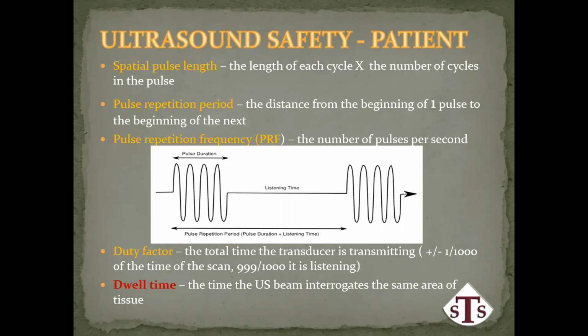That listening time will alter according to the depth that you have set for your image, because you cannot send out the second pulse until all the echoes have come back from the first pulse. The machine would not be able to calculate which echo came from which pulse. Now, the duty factor is the time that the transducer is transmitting. And in our pulse echo system, it's only transmitting for approximately 1/1000th of the time that you are scanning. And the other 999/1000ths is when it's listening.